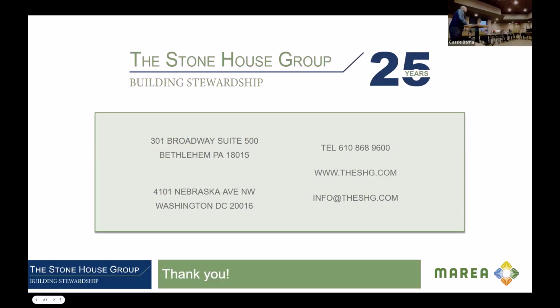Yes. There are some rules on the geo exchange tax credits that 75% of the energy over the year had to be produced by the geo well to qualify for the credit. So the systems we're seeing that get the credit are going to be 75%. That means you don't have to put in the cost of the peak load with the new systems. You can use some of your old base loading machines, gas for example, to help on the really cold day and still get the tax credit. So yes, we're seeing hybrid plants in lots of ways.